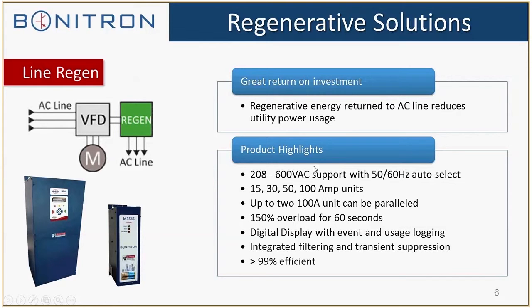All of our units are rated from 208 to 600 volt AC with a 50 to 60 Hz auto-select. The line regeneration modules automatically sync to the line, so whether it's 50 or 60 Hz, the maintenance guys don't have to go in and select that themselves — they just plug up the unit and it's going to sync to the line. All Bonitron line regen units have integrated filtering and transient suppression. Enclosed in each unit is a line load reactor along with snubber boards and other components to clean the power that's put back into the facility, making it a 99% efficient module.